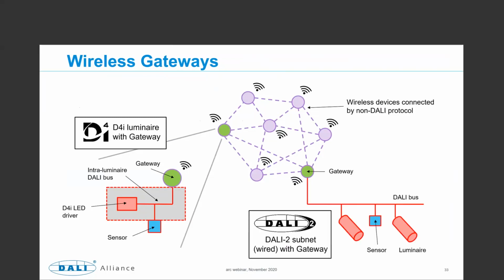You can do the same thing for an existing wired DALI bus, so DALI-2 subnet wired with gateway, where you might have a sensor and some luminaires in a room, for example. The gateway does the translation between DALI and Zigbee, or DALI and Bluetooth mesh lighting. I'd highlight here that there's a potential limitation, but it's on the network side. The reason we're standardizing these things is to ensure the mapping is consistent, and the behavior is always the same on the DALI side.